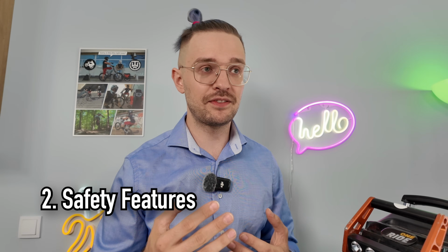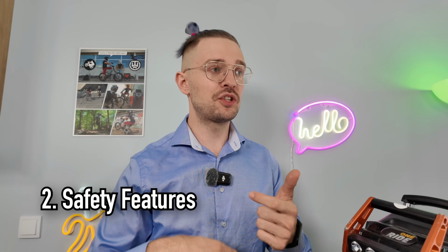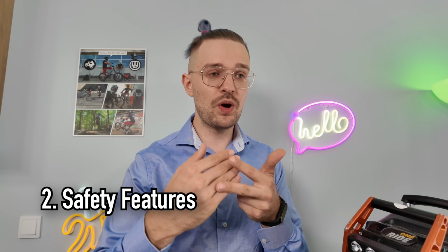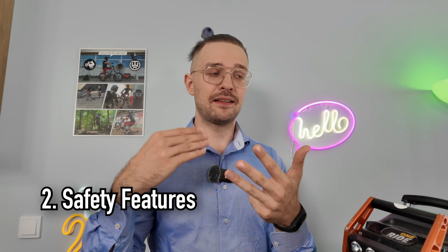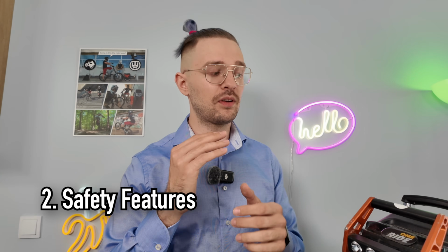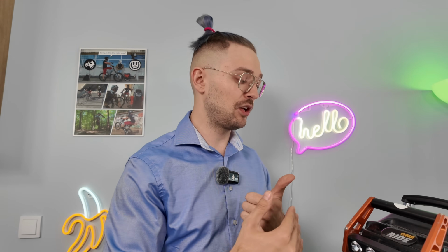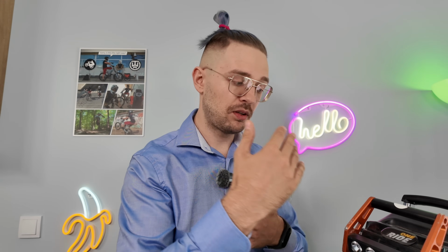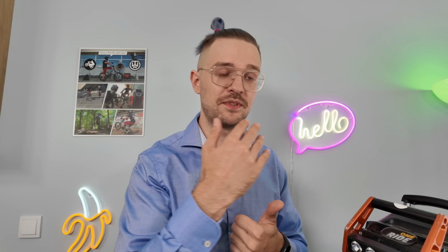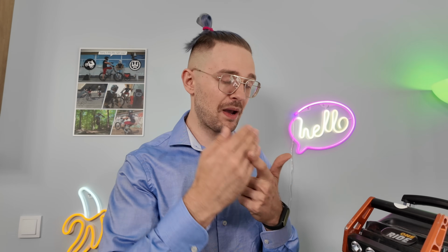The second important aspect is safety from overcharge, overcurrent, too high temperature, and short circuits. A good BMS should include either MOSFETs or proper fuses to make sure there won't be any short circuit in the battery, or the cells blowing. There should be battery temperature sensors inside to make sure it's not running too hot, and in cold climates that you're not charging it when it's too cold.